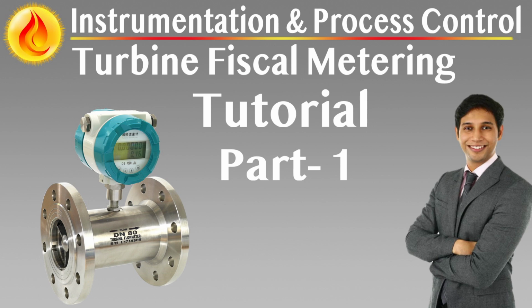Uncertainty compliance and system integrity. Turbine meters and all secondary instrumentation must meet the overall metering system's uncertainty specification. Components cannot compensate for each other. Errors must not cancel out. A transmitter reading low cannot be accepted simply because a turbine meter reads high. Each component must independently comply with its maximum permissible error. The system must be free from compensatory errors to retain certification.